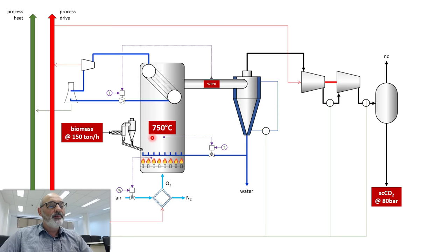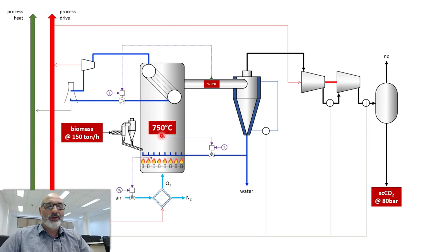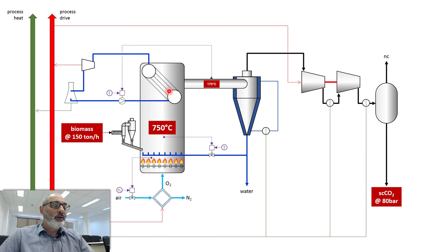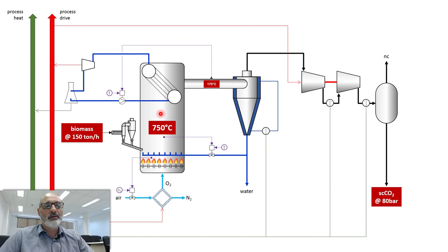Another parameter we're going to fix is the combustion temperature. We want to prevent the formation of nitrogen oxides, which are important pollutants. We also want to keep the temperature low enough for the materials used in the boiler — especially in the tubes — to be affordable. If the temperature is excessively high, we have to use special materials, and this equipment is going to cost a lot. So it's also an economical consideration.